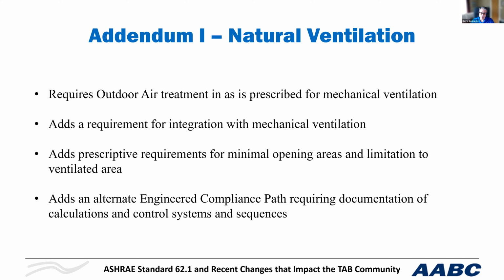And an additional thing: if you do not follow the prescriptive requirement and you have an engineered system, then the engineer must show his calculations on design documents, and more importantly, the control methods of how he's going to maintain that. So if you are going to have operable openings for natural ventilation, you have to show that the controls are going to open them whenever the space is occupied, and so forth. So bottom line, again, there should be more TAB involvement in these systems.